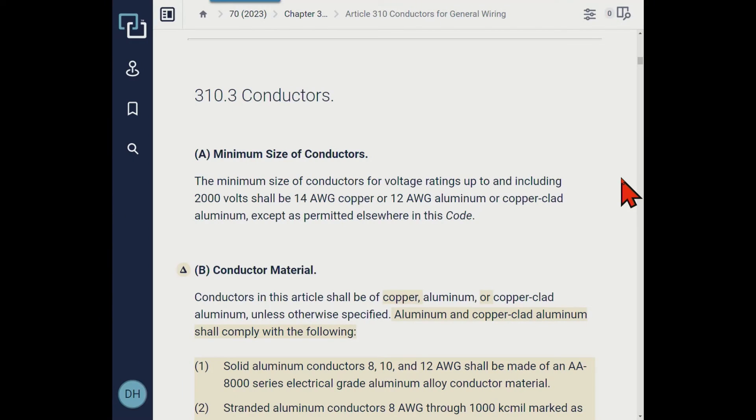If you had a wire rated for 10 amperes and a breaker rated for 10 amperes, and you comply with 210.12 and 210.23, and possibly 210.19 for 10 ampere circuits, then you could use it — if we knew what the ampacity was. The question is why the code added all these rules. Let's go to 310.3, which defines the smallest size wire the code allows us to use: 14 gauge copper and 12 gauge aluminum or copper clad.